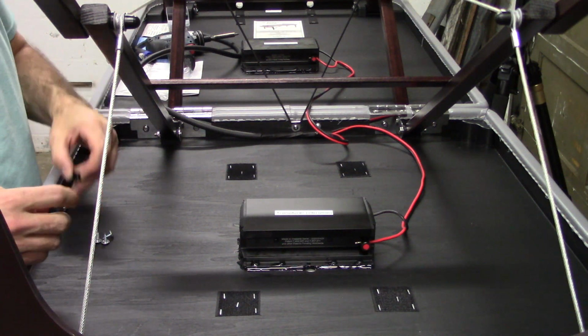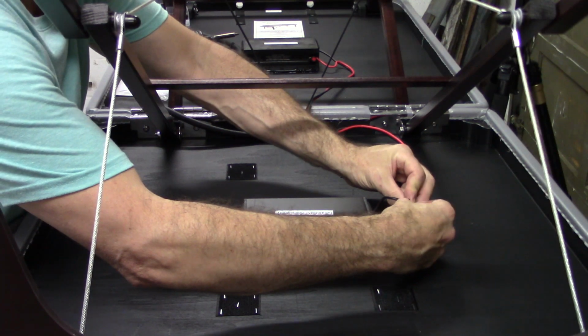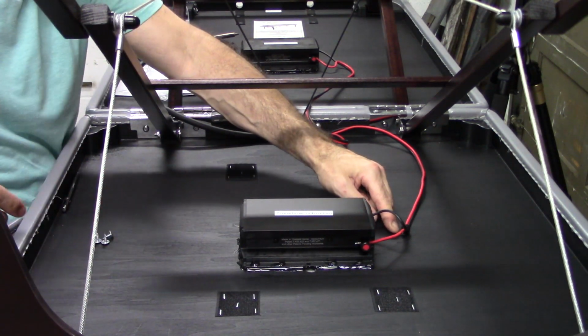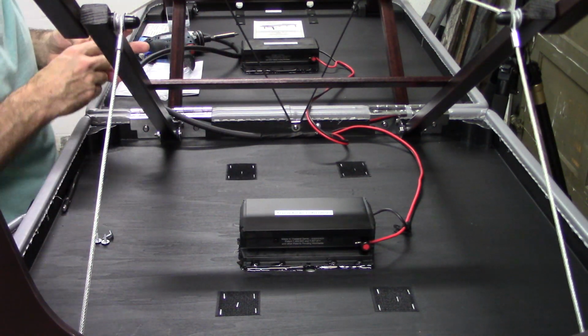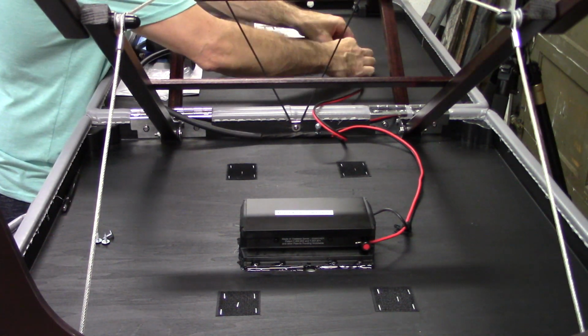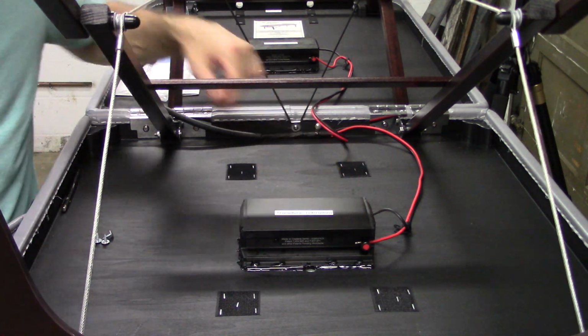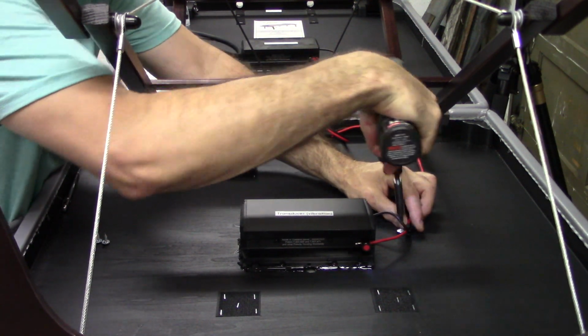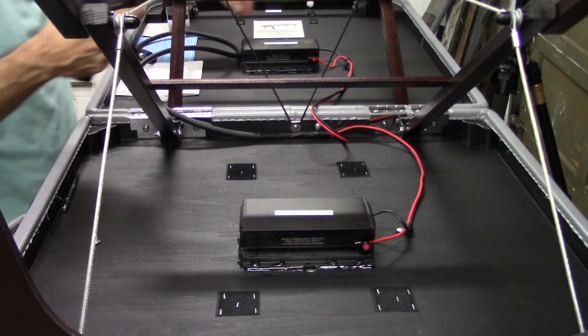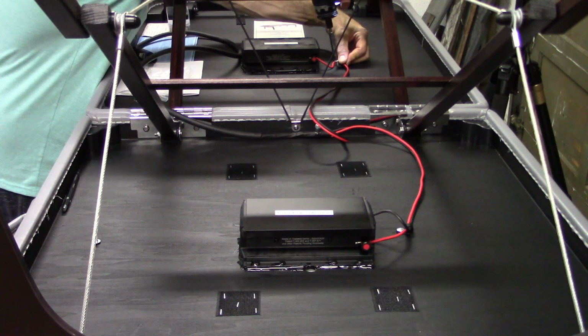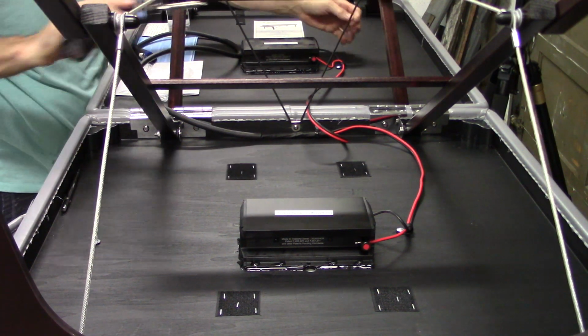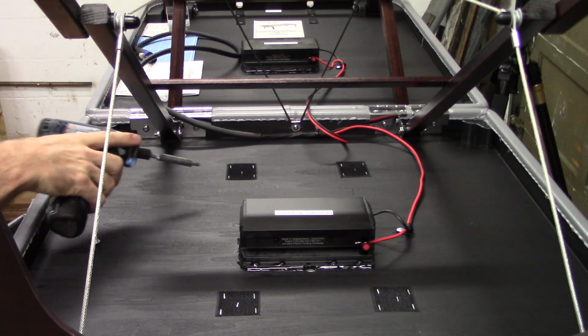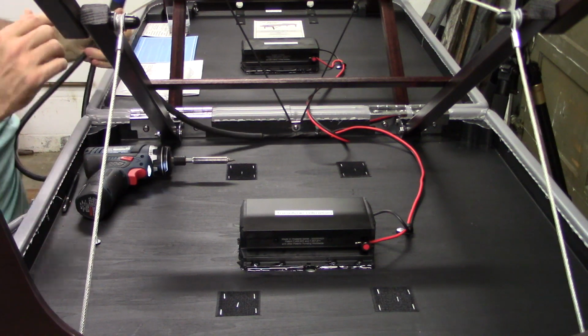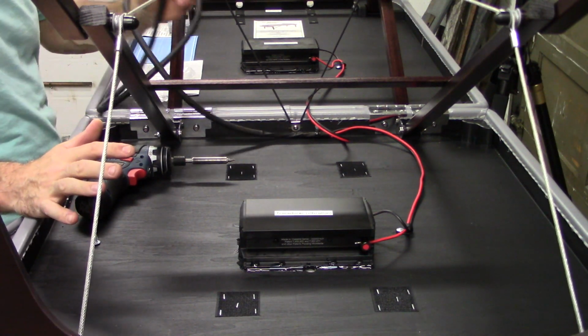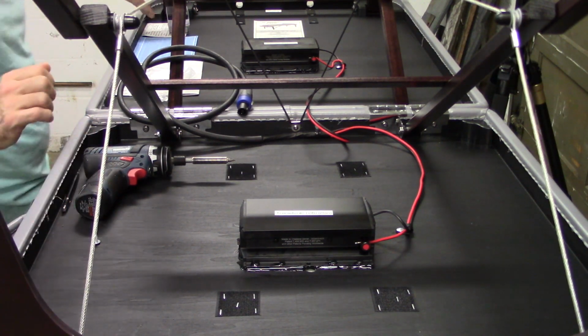We have a few other cable clamps left over. We're going to take those cable clamps and we're just going to apply them right onto the part. It's about 3 inches away from the transducer. And the reason why we're doing that is just to keep the cable in a nice, neat area. And that is it for the installation. You can let it dry. It's going to take approximately an hour to fully cure. Well, 24 hours to fully cure, but an hour before you can start moving it around.